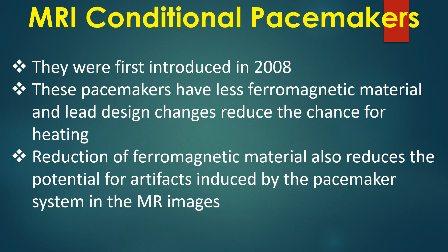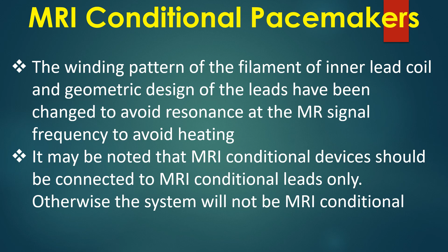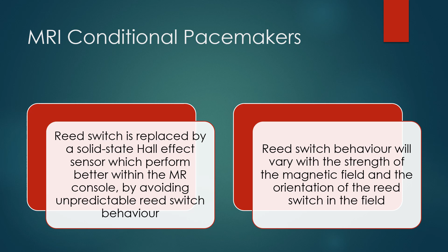The winding pattern of the filament of inner lead coil and geometric design of the leads have been changed to avoid resonance at the MR signal frequency to avoid heating. It may be noted that MRI conditional devices should be connected to MRI conditional leads only. Otherwise, the system will not be MRI conditional. Reed switch is replaced by a solid state Hall effect sensor which perform better within the MR console by avoiding unpredictable reed switch behavior. Reed switch behavior will vary with the strength of the magnetic field and the orientation of the reed switch in the field.